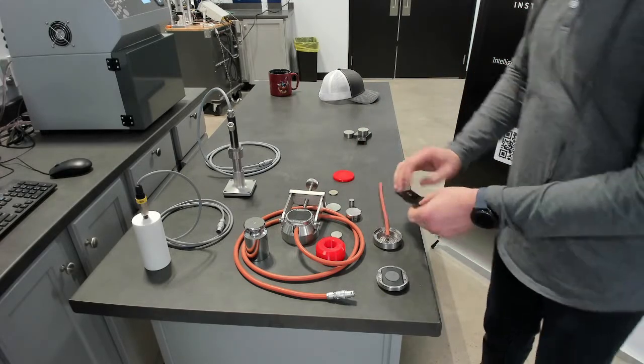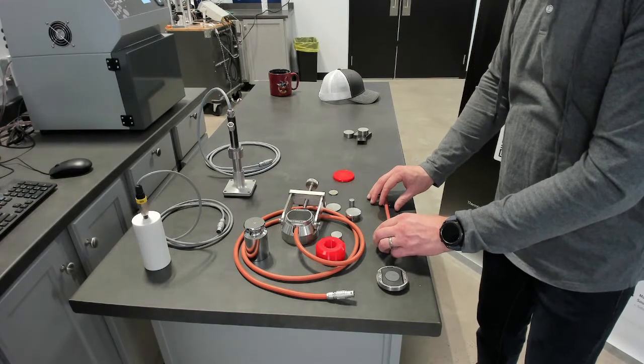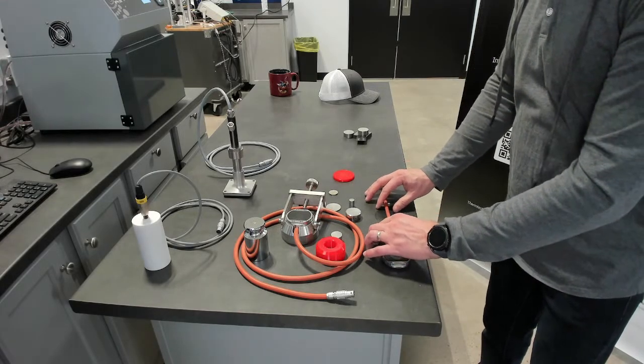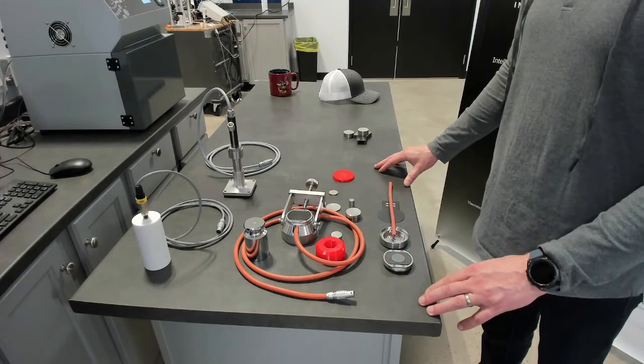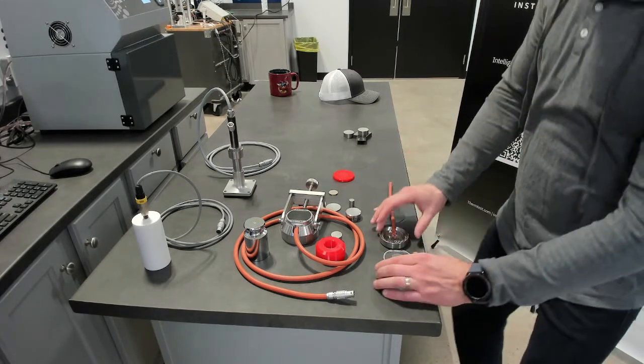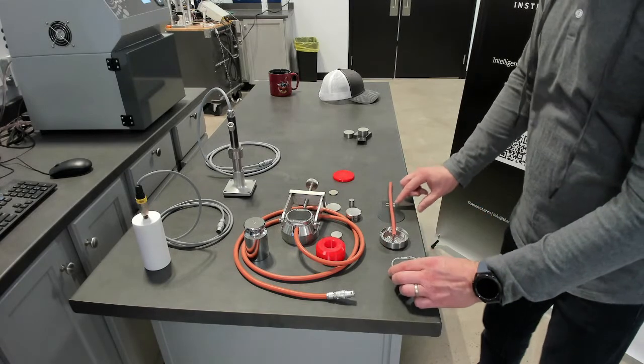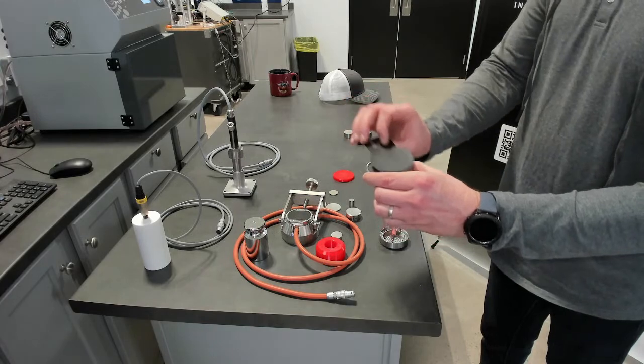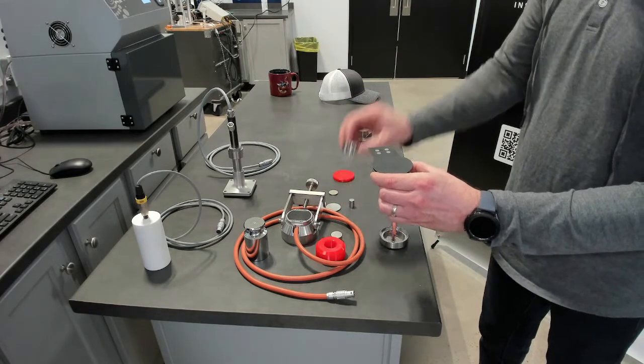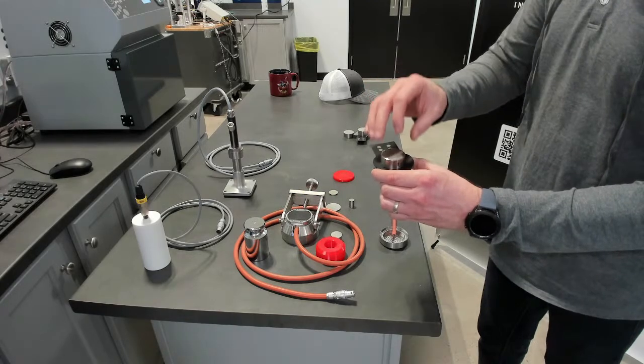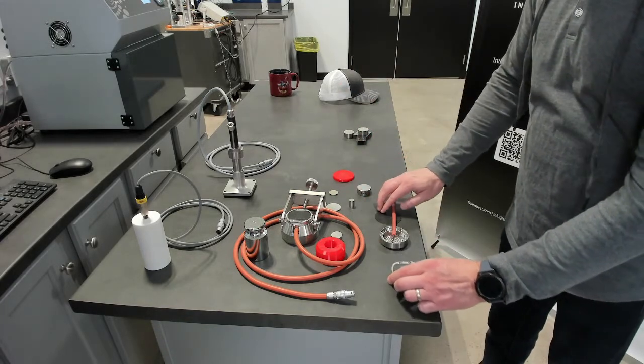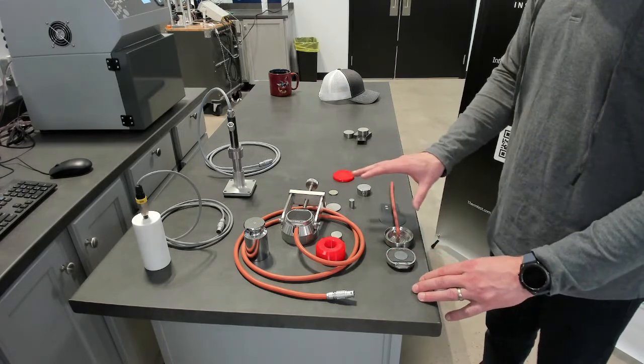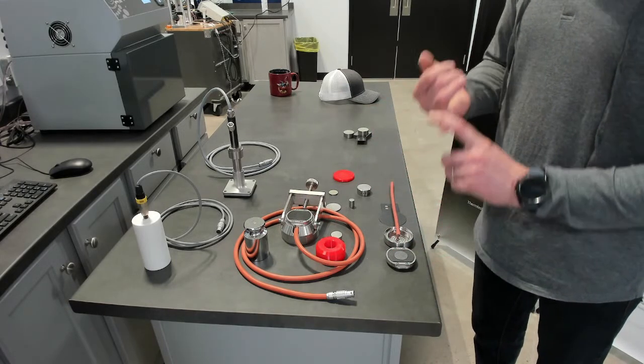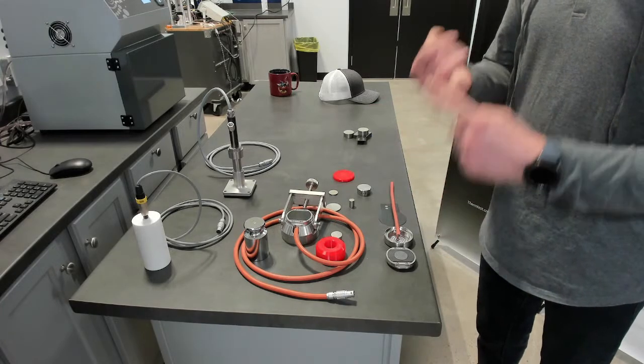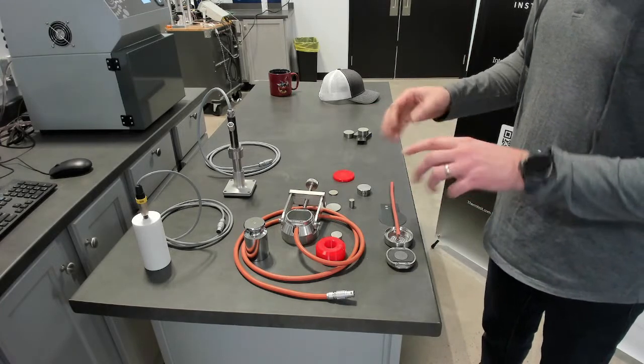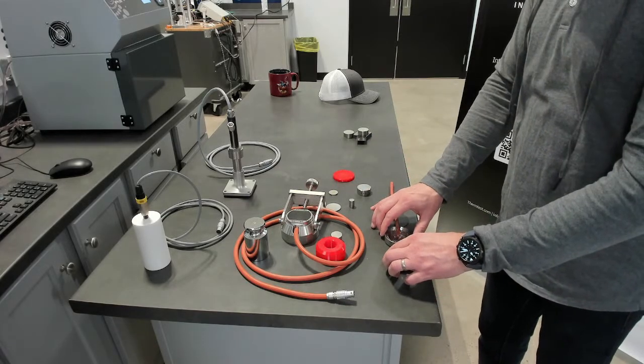So I invite you, in terms of construction of the sensor or seeing what sensors are made of, to ask any maker of modified transient plane source to do the same. If they can take it apart and show you that the basic principles are still insulation, sensor, and sample, just configured conveniently, following ideal theory, so you don't need a contact agent, and you still have all the strengths of varying test time, direct properties for thermal conductivity and thermal diffusivity, and calculated specific heat. All that ideal theory applies. So it's a really strong capability we've added to this.